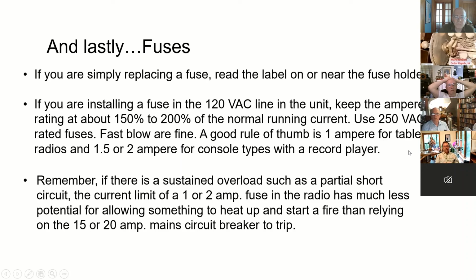If the fuse tries to open a short circuit, 120 volts AC can arc across that little gap. You'll want to use a regular 250 volt rated fuse. Fast blows, I've never had a problem with them. Good rule of thumb is 1 amp for tabletop radios. You can go less, but they're kind of hard to find, and the National Electrical Code generally recognizes a 1 amp fuse as being minimum standard size. You would pick the next size up from the running current. You got a record player or something like that, you might want to go with a 1.5 or 2 amp.